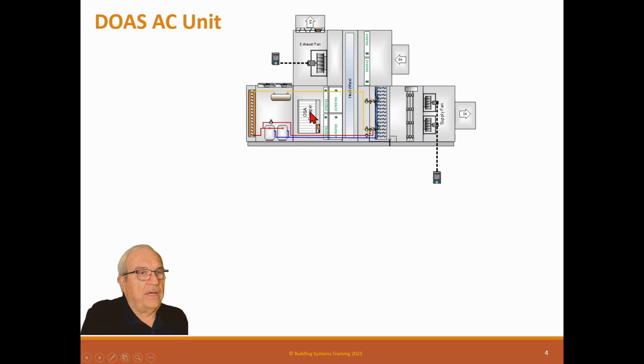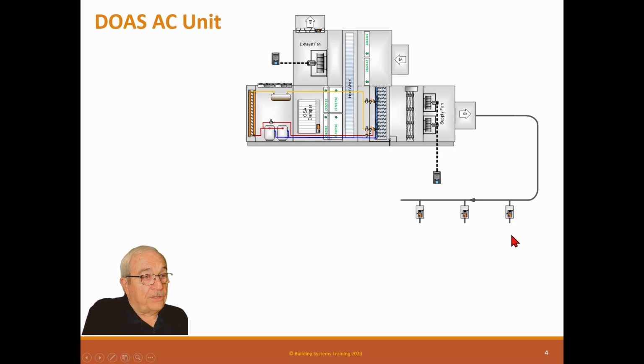In this case, we have inlet air coming in here, going through the filter bank, through the heat wheel, through an air conditioning coil, through a heat strip, and out to the building. And this ductwork out to the building has a bunch of dampers that are inlet dampers to other air conditioning systems, and these are their outside air systems. These could be just dampers controlled by that package unit, or these could actually be VAV boxes that are set up to be constant volume, so that gives it that constant volume outside air to the unit.